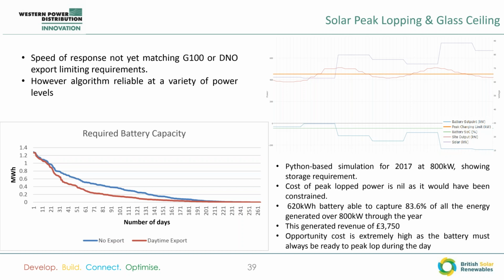So on the sunniest days, you would need 1.2 megawatt hour of storage to be able to capture all generation and constrain the output to 800 kilowatts. However, a 620 kilowatt hour battery is able to capture over 80% of all that energy. So doubling it to 1.2 would be a significant waste of money. You wouldn't be able to get the use out of the battery.